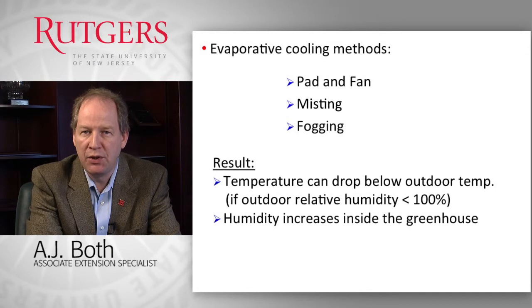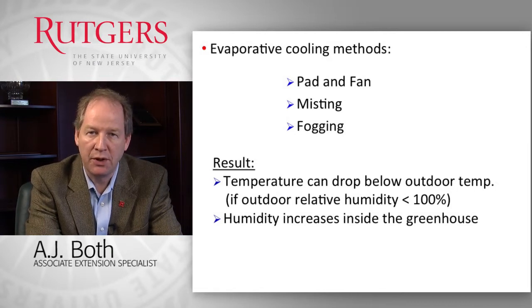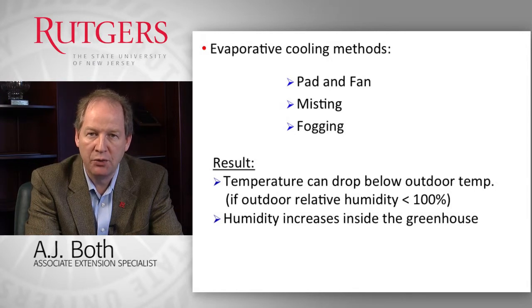There are several ways that we can use evaporative cooling in greenhouse applications. The first one is the pad and fan system, followed by misting and fogging. By evaporative cooling we drop the outdoor temperature as it comes into the greenhouse — that is, if the outdoor temperature or the incoming air is not already saturated, because if it is already saturated we can no longer evaporate more moisture into it. By doing this process of evaporation we increase the overall humidity inside the greenhouse, so this could be an issue depending on what strategy you want to use to grow your crops.